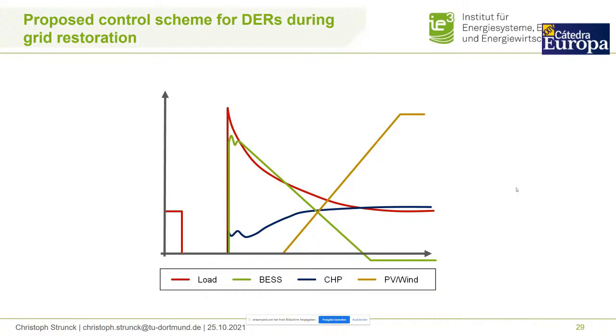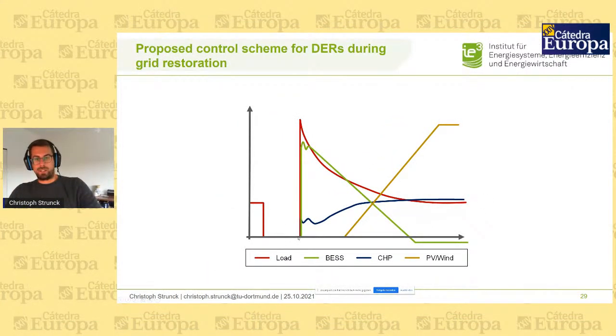During a grid restoration, it is also very important to have a control scheme for your participating generators, because without that it is not possible to restore the grid. Here in red there is an example for the load, where we also see the cold load pickup - at the beginning it is pretty high and then declining. We need some fast-acting generation units, like battery storages, in the beginning to provide the necessary power to the grid.